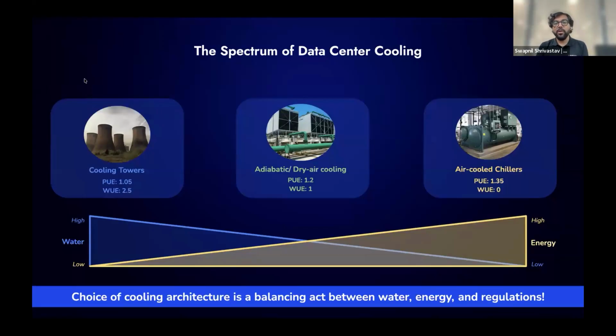So if you look at the whole spectrum of data center cooling solutions today, you have at one end cooling towers, which consume a lot of water, almost 60 to 80,000 liters per day per megawatt. So very high water usage effectiveness, but they're low on energy and low carbon, with a very high amount of water. On the other end, you have air cooled chillers, where you can call yourself waterless or zero water, but then your PUE or energy consumption becomes very high. And again, you have to design for peak loads. That means your capex, power distribution, everything becomes an even higher investment.